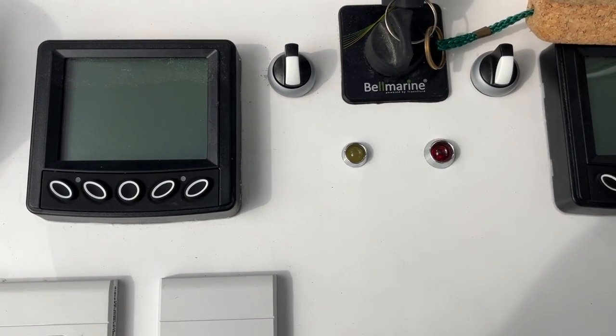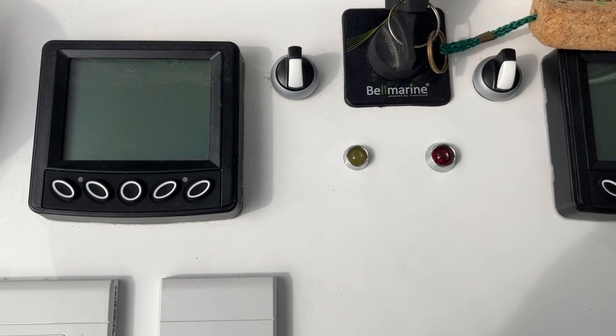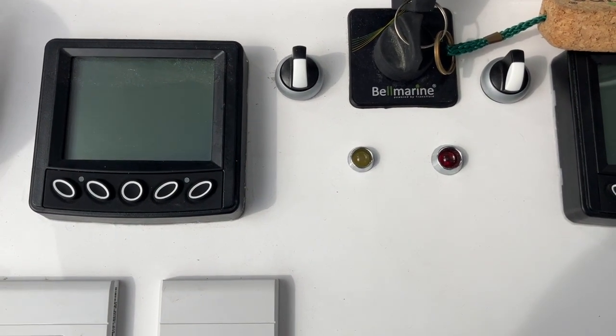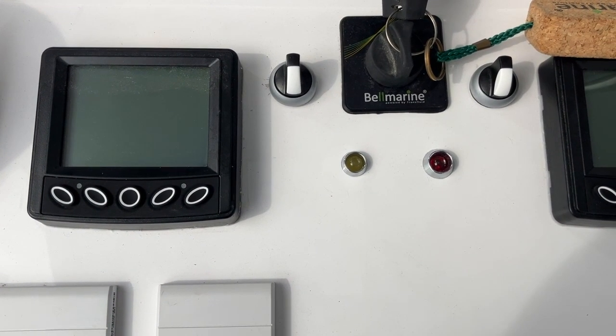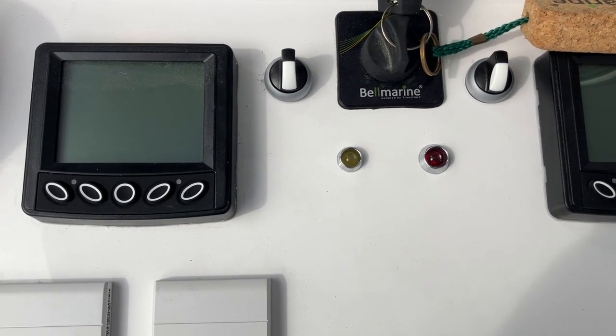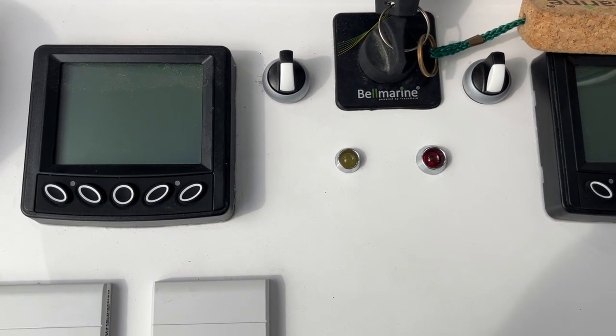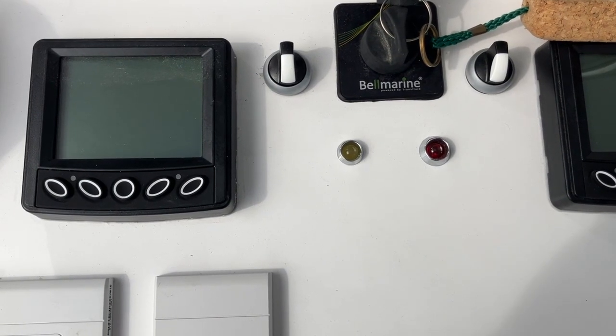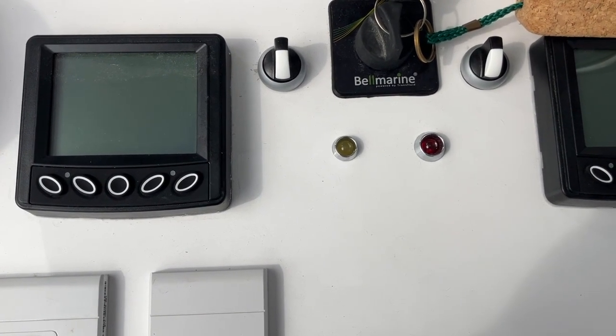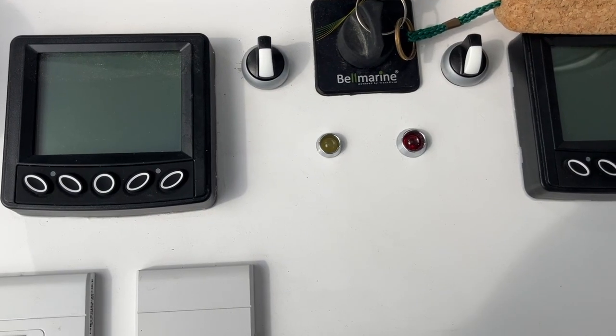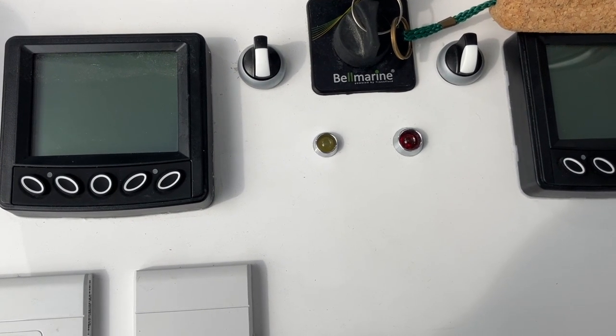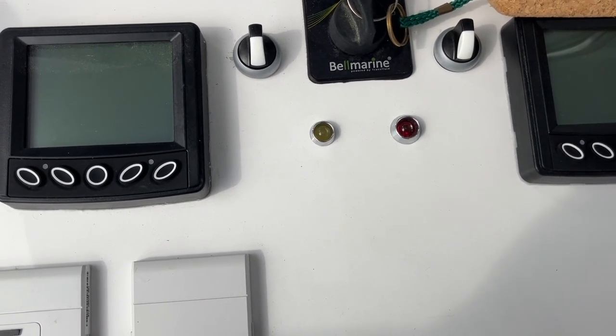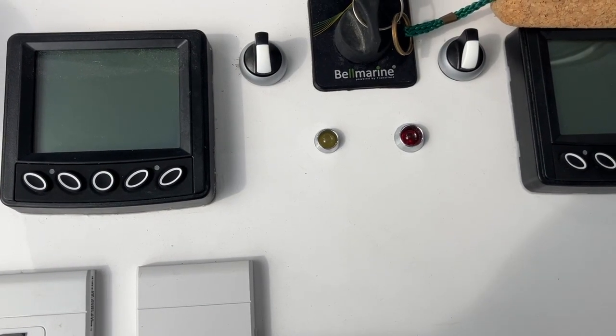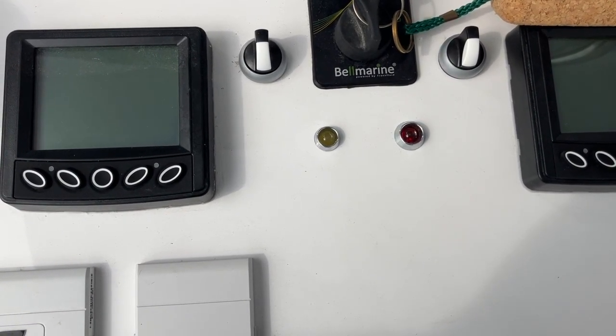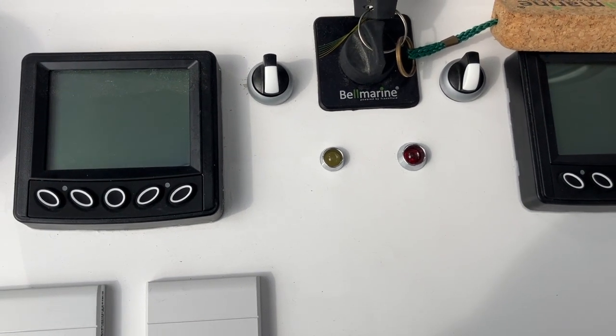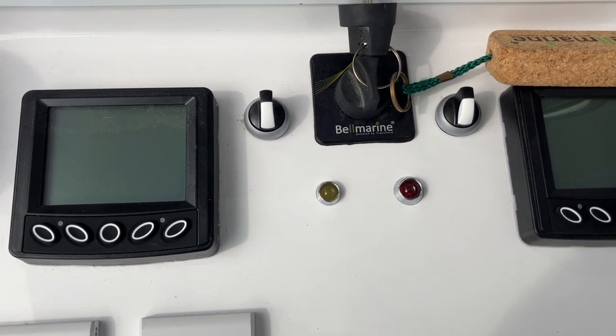It's also interlinked with the load shed system. At the same time this light comes on at 50%, the 48 volt battery bank will stop charging the 12 volt battery bank if that's what it's been asked to do. Any loads on the load shed system, like the hot water system, won't be heated by the inverter's 240, and that will shut down until the battery capacity is brought back up to 85%. Then it gives you back that capability. So that's how that all works.